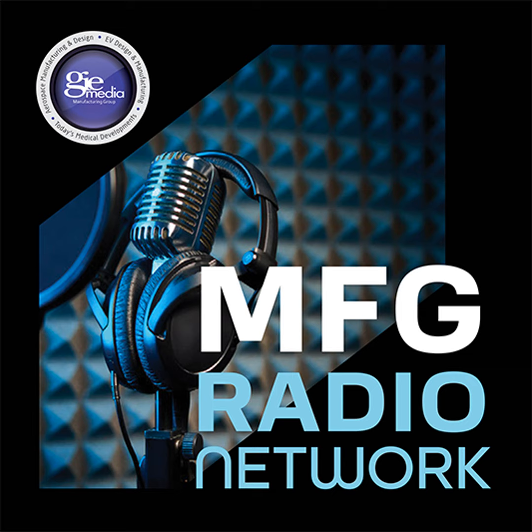From there, we're able to transition into our scanning electron microscopes. Typically, this would be done under our Zeiss Evo microscope. This is our conventional scanning electron microscope. It has either a tungsten or a LaB6 filament and can be equipped with any number of different particle analysis detectors that run our SmartPI software, Smart Particle Investigator. Very intuitive software designed to be able to easily detect your particles and do the elemental analysis to give you that chemical composition. This can also be done under our field emission scanning electron microscope, the Zeiss Sigma.